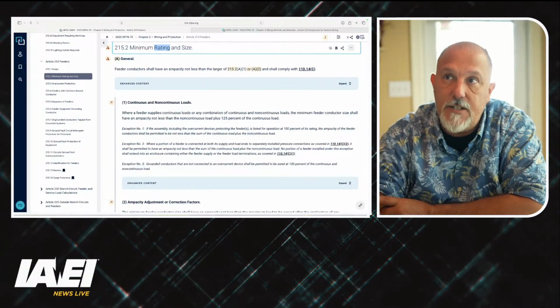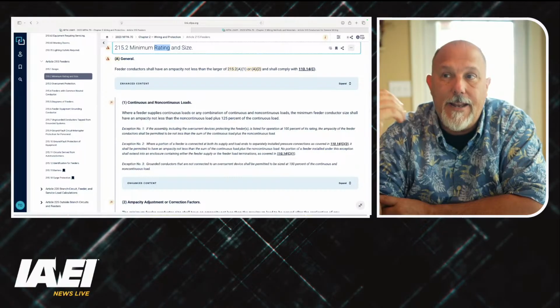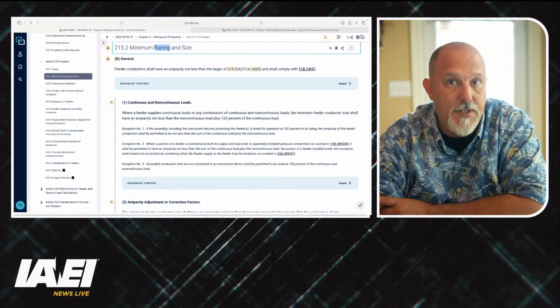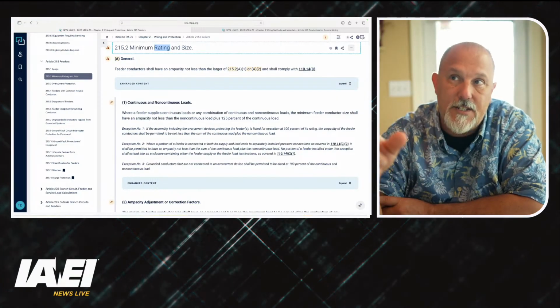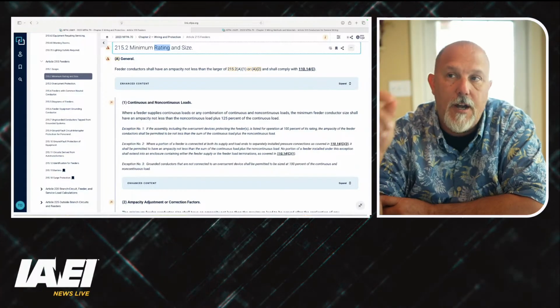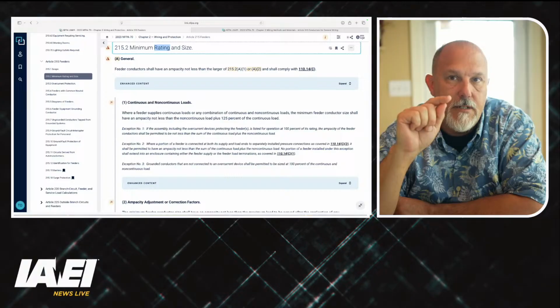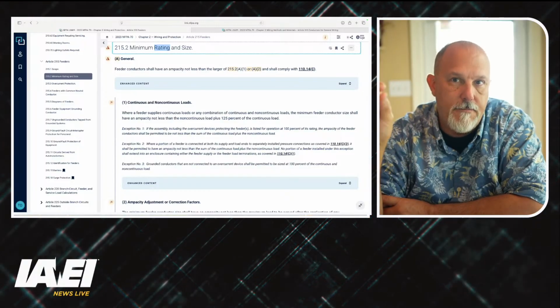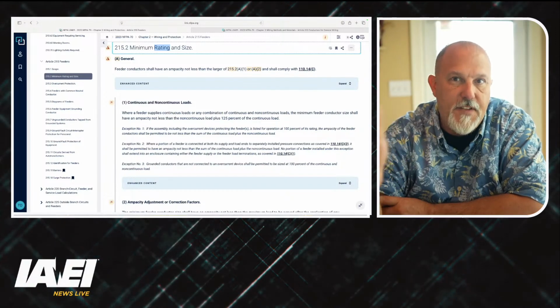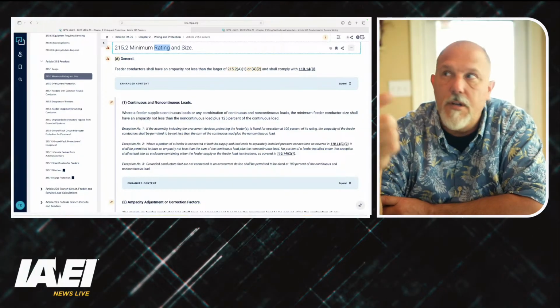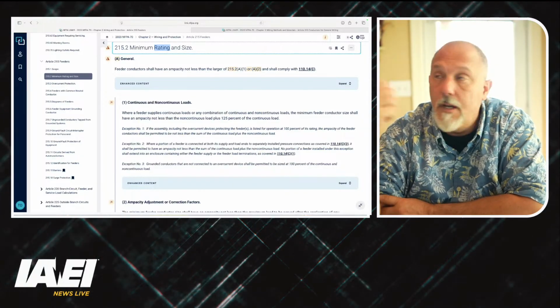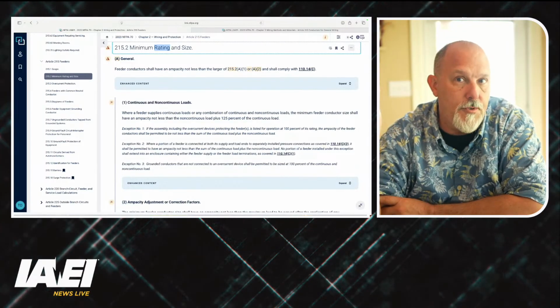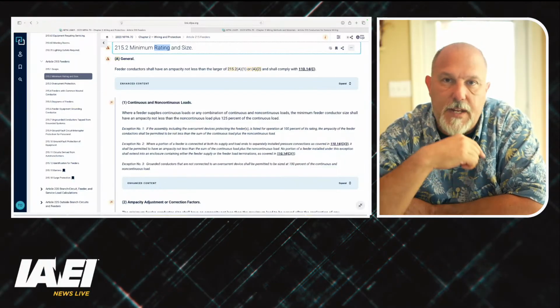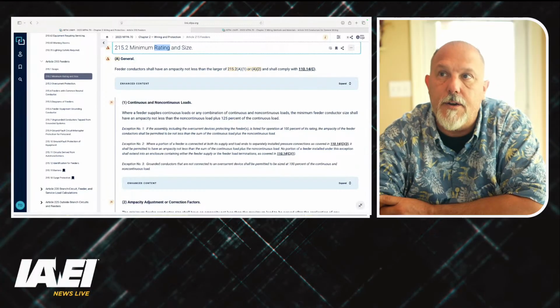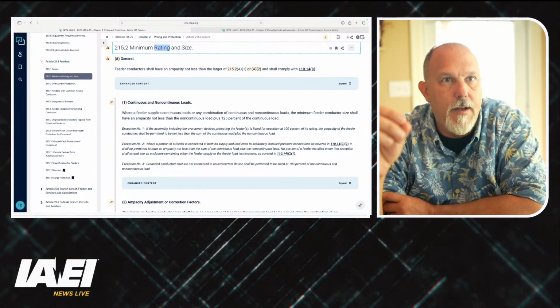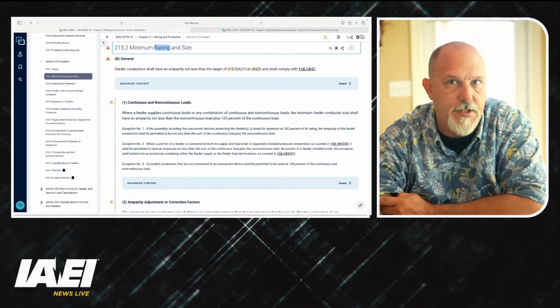But you're going to see 215.2A1 and A2 are the same two type of calculations that we just did for a branch circuit. So regardless of whether or not this is a branch circuit or a feeder, I have the same process. The difference is going to be how I determine the load current. If I have a branch circuit feeding HVAC, feeding a motor, feeding an oven, any type of specific loads. Now, outside of, if I have a branch circuit that's feeding 14 receptacles, that's a little different on how I handle that. But the branch circuit, I'm going to determine the load based upon what that branch circuit is serving.